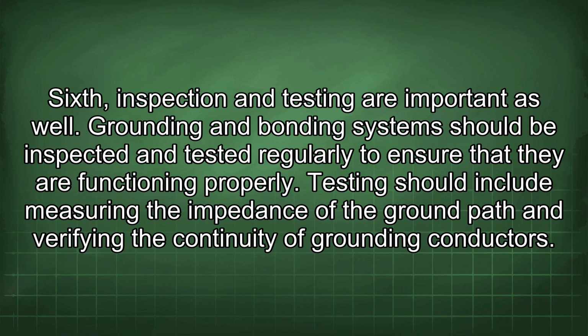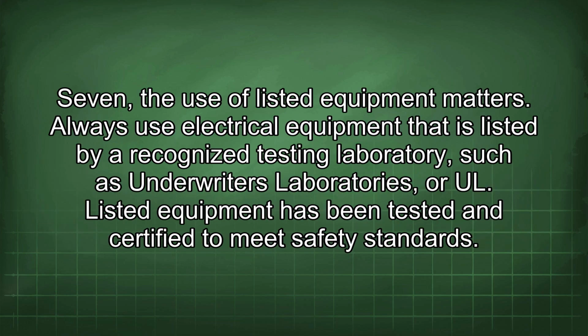Grounding and bonding systems should be inspected and tested regularly to ensure that they are functioning properly. Testing should include measuring the impedance of the ground path and verifying the continuity of grounding conductors. Seventh, the use of listed equipment matters. Always use electrical equipment that is listed by a recognized testing laboratory, such as Underwriters Laboratories or UL. Listed equipment has been tested and certified to meet safety standards.